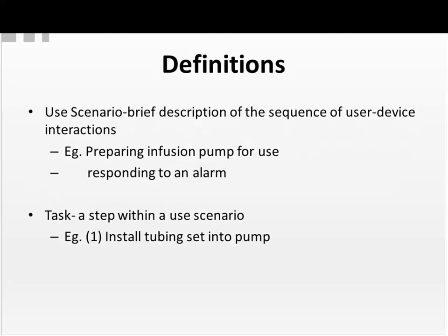Let's go through some definitions, and then we'll get into the procedures. A use scenario. It's a brief description of the sequence of user-device interactions. It's a small story. Example, preparing an infusion pump for use is a use scenario. It's a small story of what you're doing.